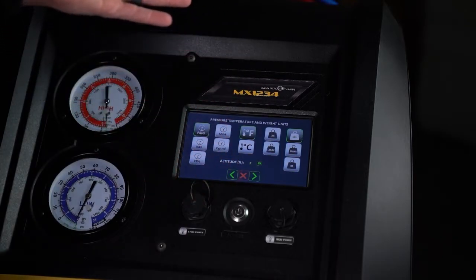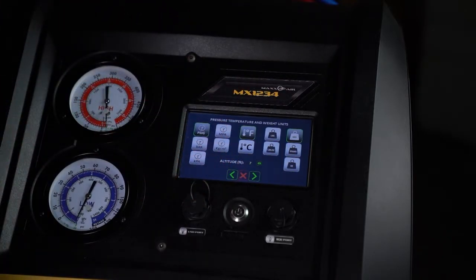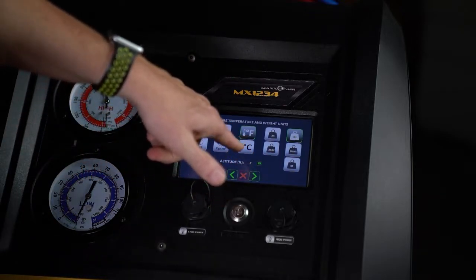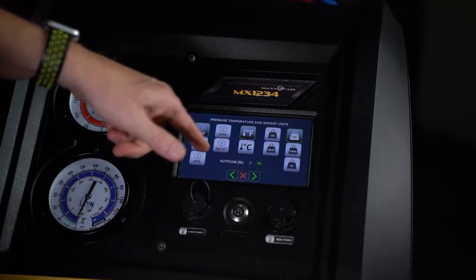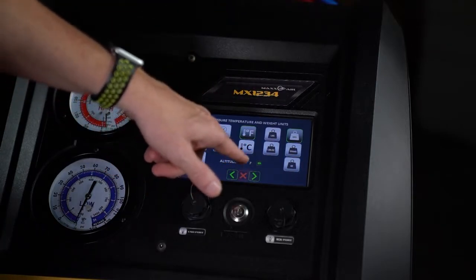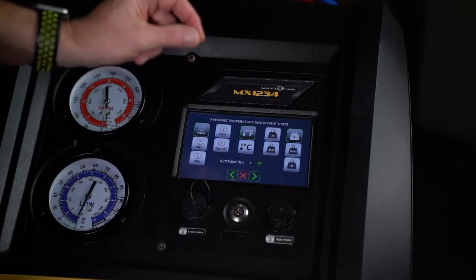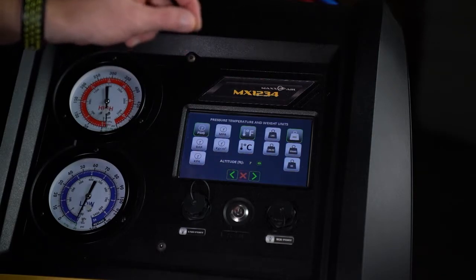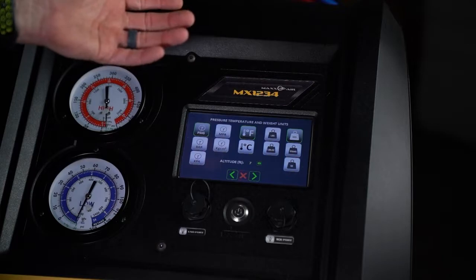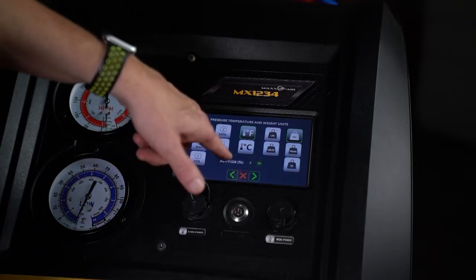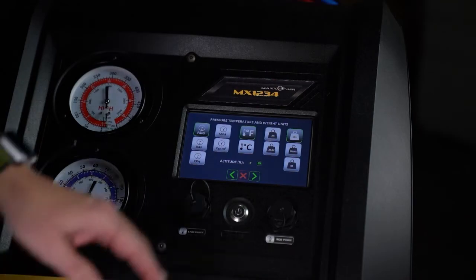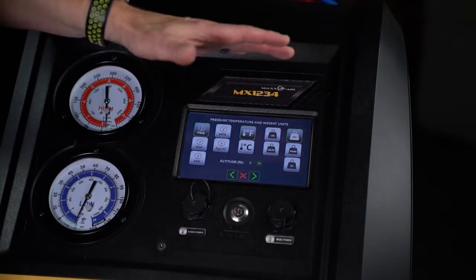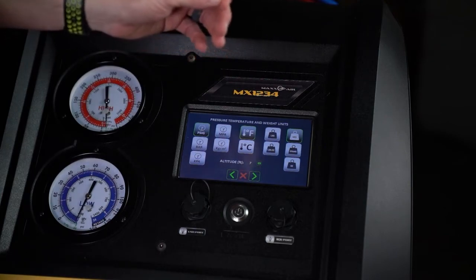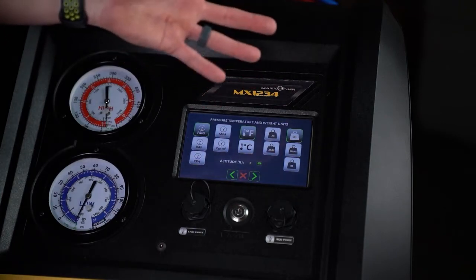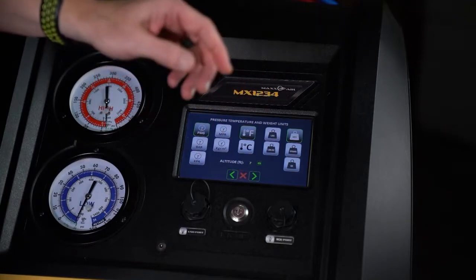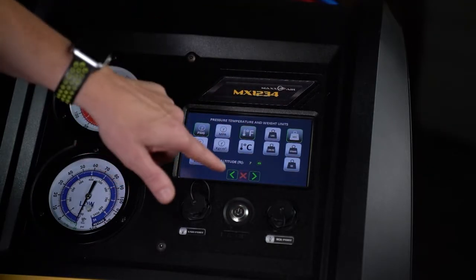Altitude: where we're currently manufacturing and setting up these MX units, we're at an altitude of about 7 feet above sea level, basically sea level. It's very important that you check the altitude of where this machine is currently being used. You can Google that information by inputting the address through a search on your phone, and it should tell you the altitude. This was not covered in previous machines' setup instructions, but we found it's highly important to make sure your altitude setting is correct.